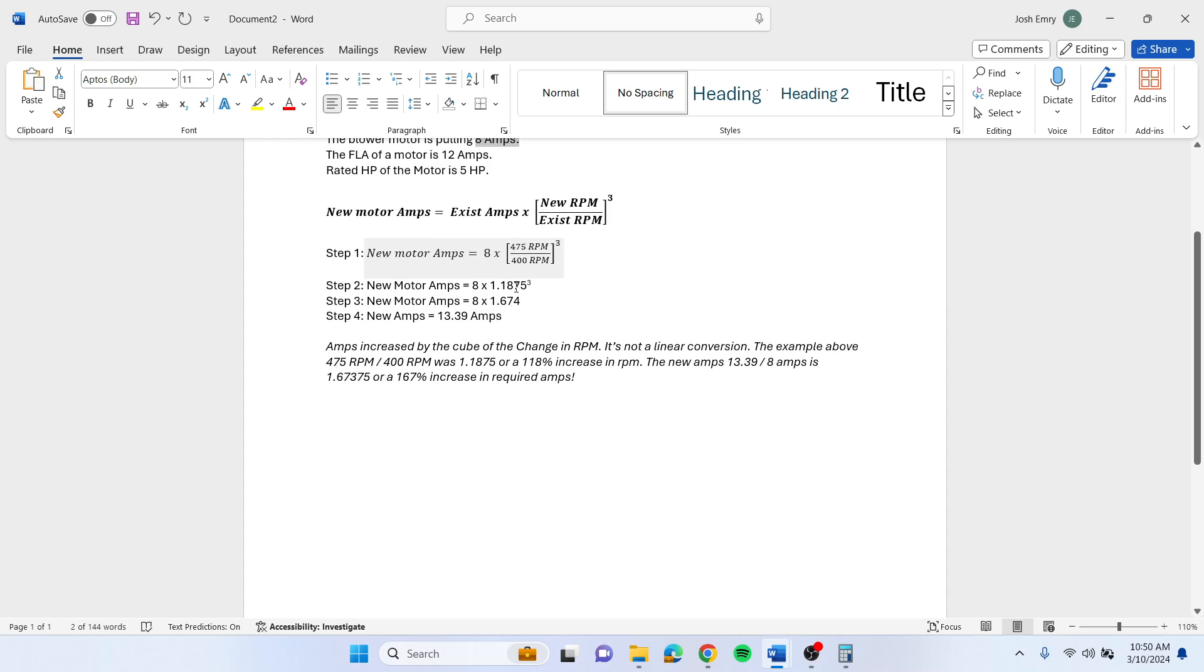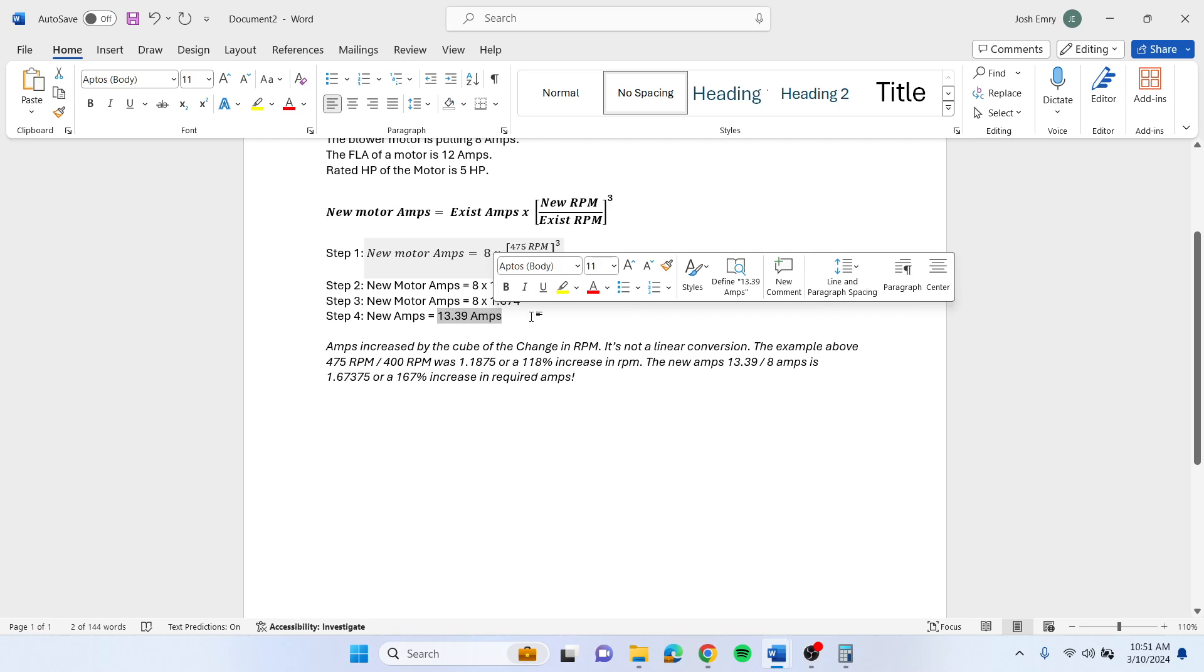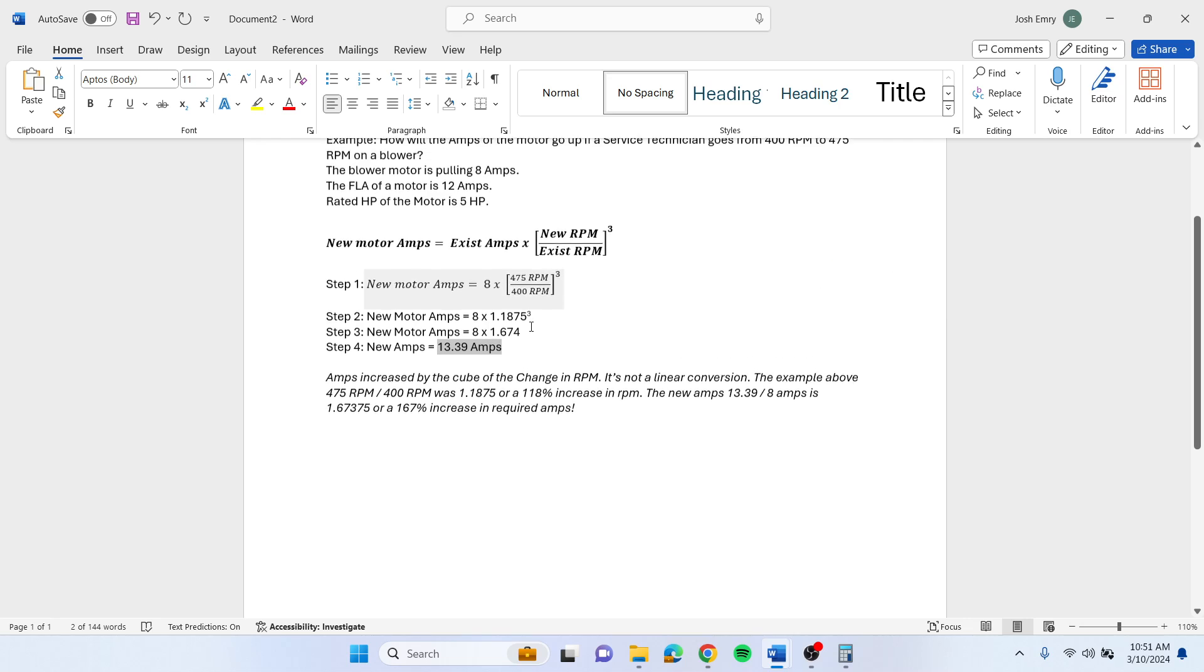So 1.1875 cubed is 1.674. Take that times 8, and you end up with your new motor amps would be 13.39 amps.